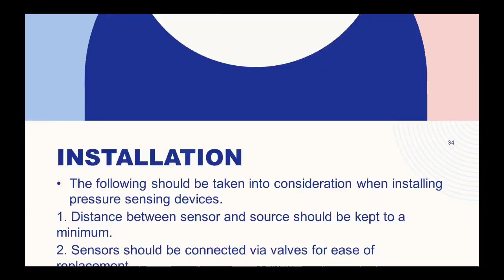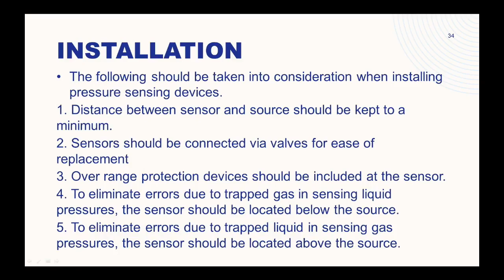So installation. The following should be taken into consideration when installing pressure sensing devices. 1. Distance between sensor and source should be kept to a minimum. Sensors should be connected via valves for ease of replacement. Overrange protection devices should be included at the sensor. To eliminate errors due to trapped gas in sensing liquid pressures, the sensor should be located below the source. To eliminate errors due to trapped liquid in sensing gas pressures, the sensor should be located above the source. When measuring pressures in corrosive fluids and gases, an inert medium is necessary between the sensor and the source, or the sensor must be corrosion resistant.